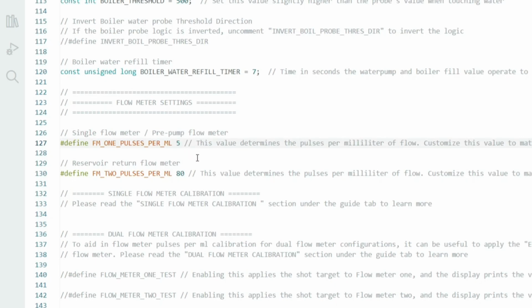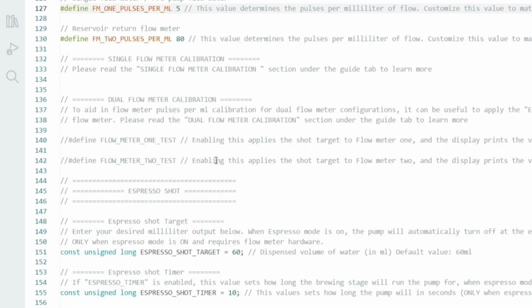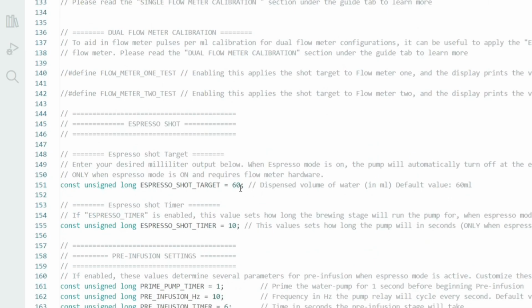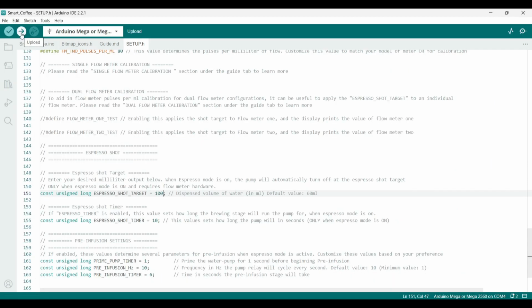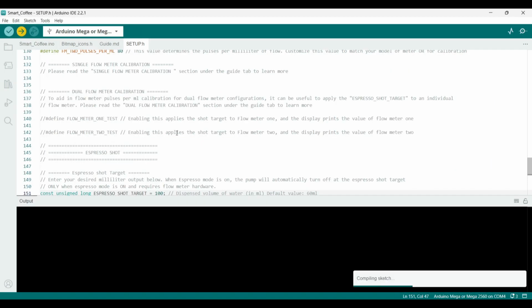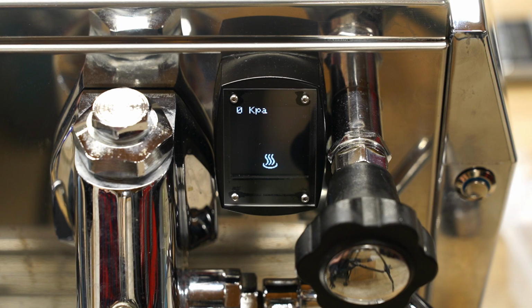I'll use the manufacturer's recommended pulses per mil value as a starting point for my calibration. Scrolling down further, I'll set my shot target at 100 mils, and now I'll upload the code. Once a flow meter is enabled, the display updates with a water counter.